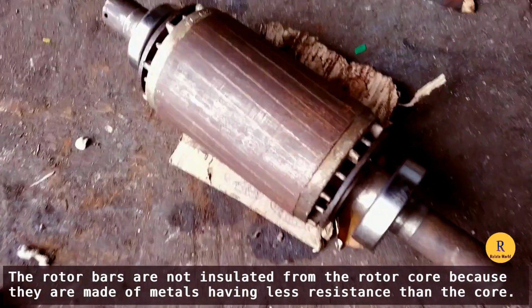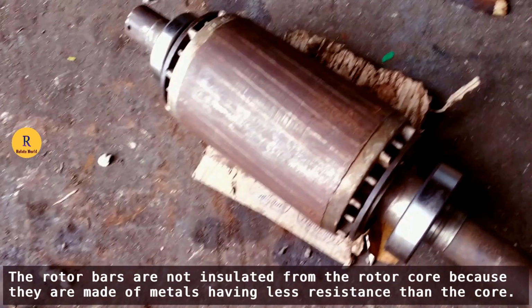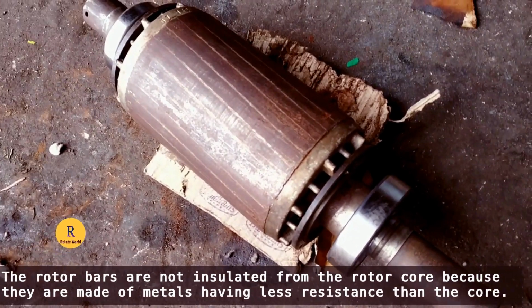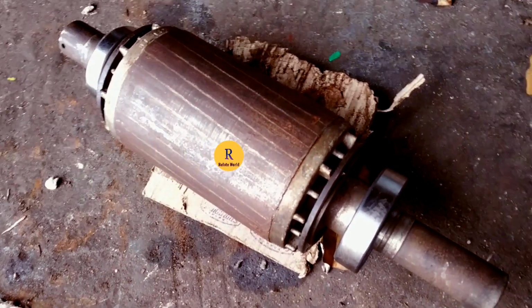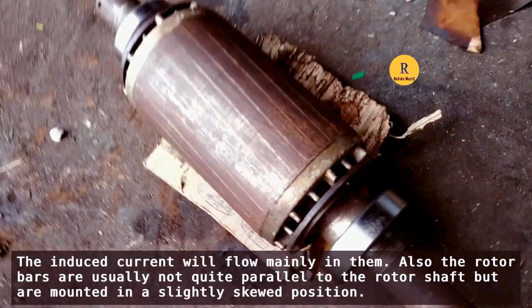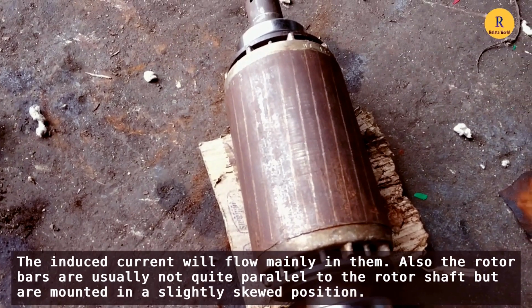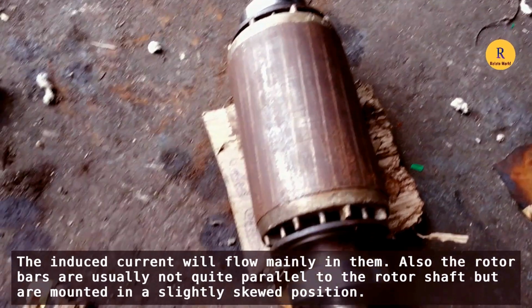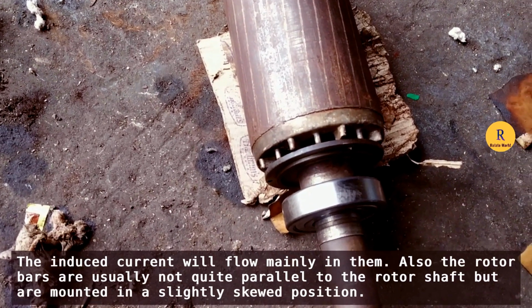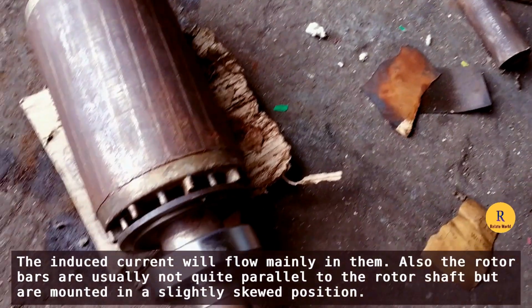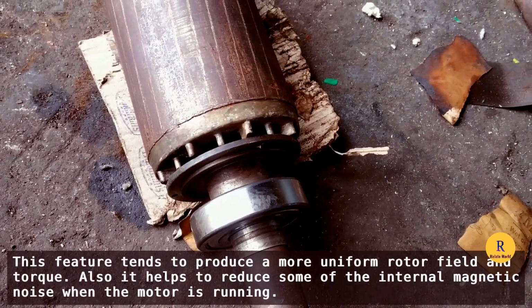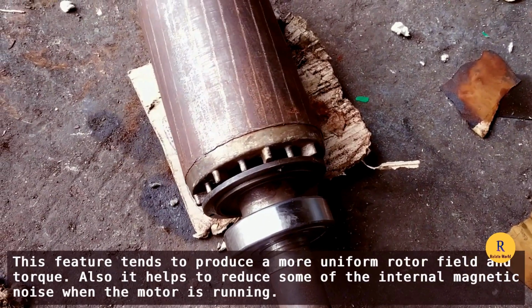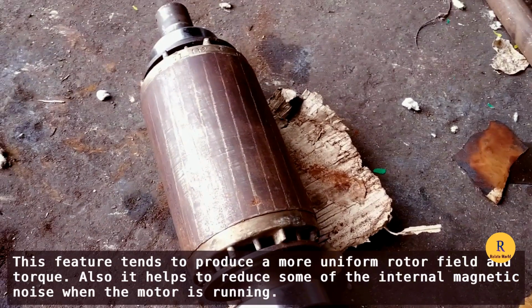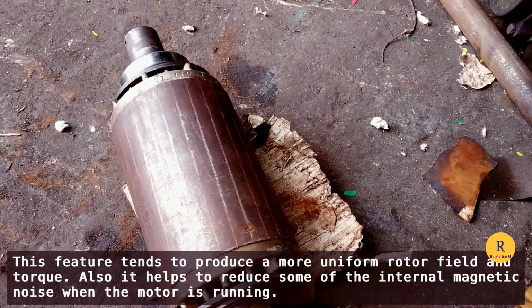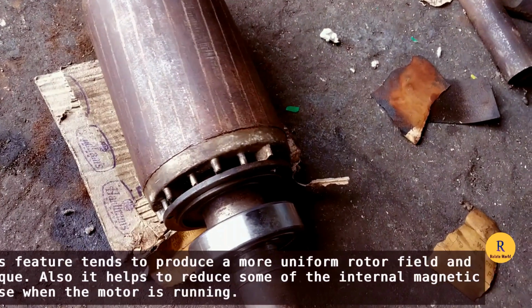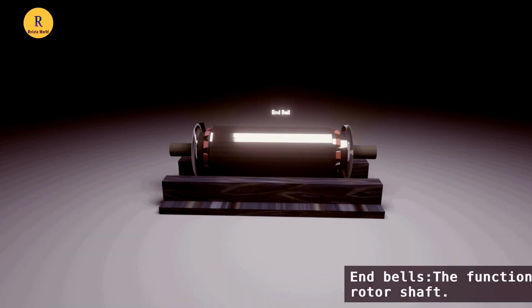The rotor bars are not insulated from the rotor core because they are made of metals having less resistance than the core. The induced current will flow mainly in them. Also, the rotor bars are usually not quite parallel to the rotor shaft but are mounted in a slightly skewed position. This feature tends to produce a more uniform rotor field and torque. Also, it helps to reduce some of the internal magnetic noise when the motor is running.